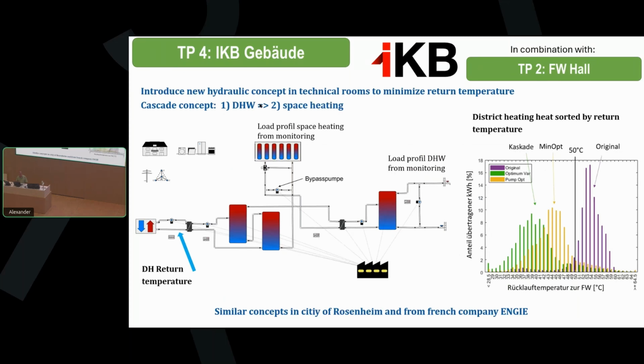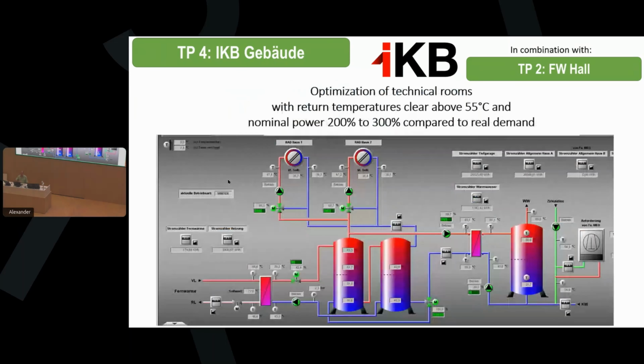One example of what we propose and would like to demonstrate is, for example, in such a residential building, typically, I go back. As you can see here in the screenshot, this is the existing building. You have the district heating station, you have the buffer storage, and from this buffer storage, in parallel, you deliver the heat to the space heating and to the hot water preparation. And typically, return temperatures from hot water with the circulation line included are very bad, very high, and also quite often, unfortunately, space heating systems have high return temperatures.